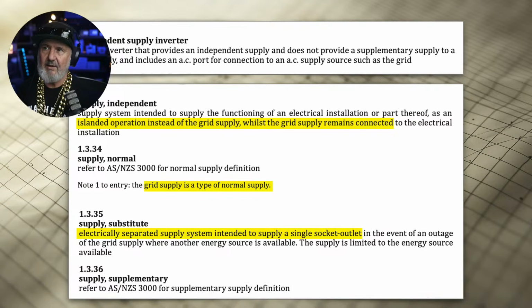Normal supply, also known as grid supply, is pretty self-explanatory, that's the grid coming in. Substitute supply is a bit of an odd one. It's an electrically separated supply with no connection, no neutral, no earth, no phase connection to the grid. It's a complete substitute, and it can only supply a single socket outlet, with a maximum capacity of 15 amps. So it's a pretty narrow definition and pretty unlikely use, but that's one of the requirements for substitute supply.